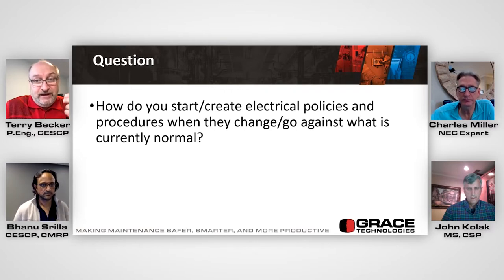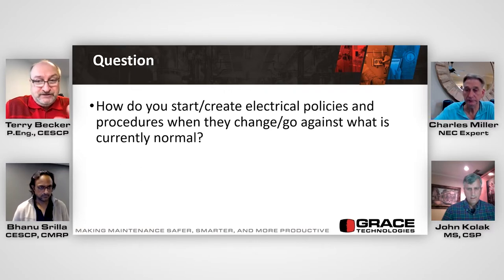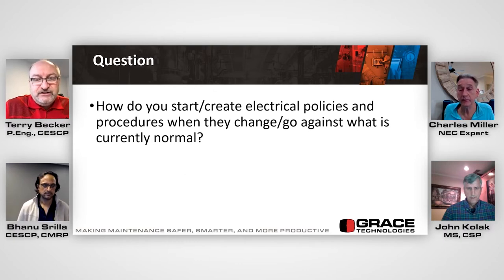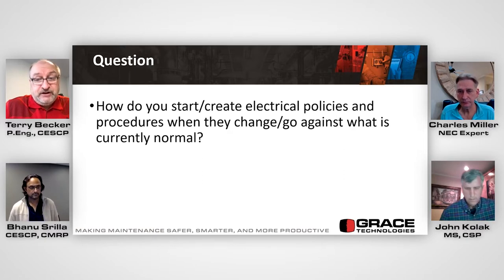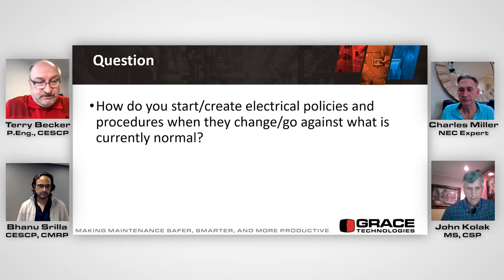So again, every 3 years you need to update because 70E and Z462 change, but they give us guidance on auditing. And then you need documentation in place for real-time monitoring by the supervisor. How do I know that the risk assessment procedure, when the shock and arc flash risk assessments, are actually being implemented by the qualified person? Because one thing they do is fill out an energized electrical job safety planning form or checklist, and then the supervisor gets that and audits it.